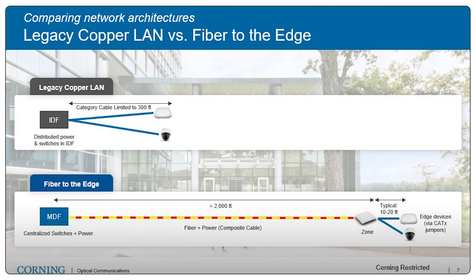Let's compare the network architectures. From a copper perspective, we are very used to repeating that architecture over and over based on that 100-meter limitation. Sometimes that repetition is just across every floor of a building, and in larger footprint buildings — such as a warehouse or factory — you may repeat it even on the same level because of that 328-foot limitation. With fiber to the edge, we can span across a large footprint building such as a manufacturing facility or warehouse without having to repeat it from one MDF or telecommunications closet, and the same applies to spanning multiple floors. It really expands the architecture and functionality we can achieve inside buildings.